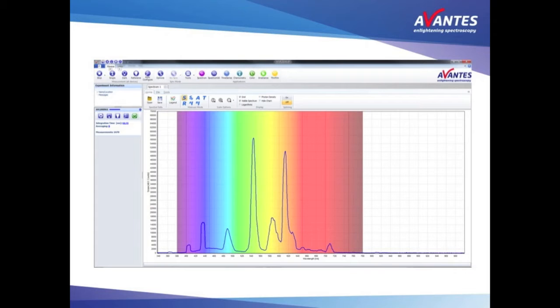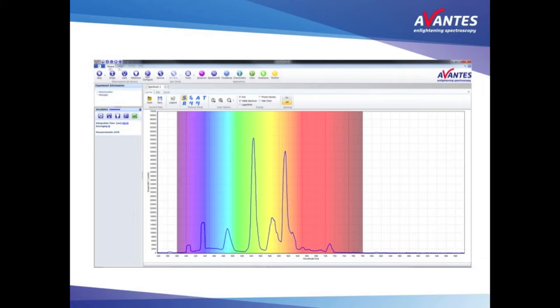This means that if a peak at 545 nm is 5 times as high as a peak at 400 nm, there is actually not 5 times more energy at 545. This is due to the detector response curve and optical properties of the mirrors, filters and fibers used.